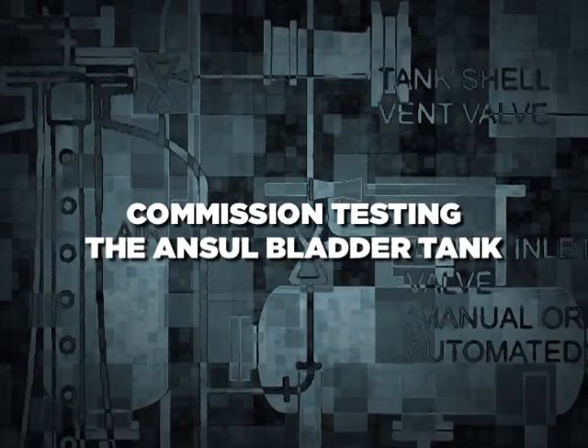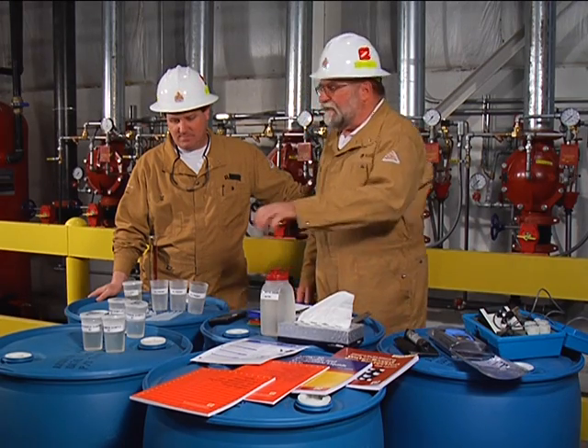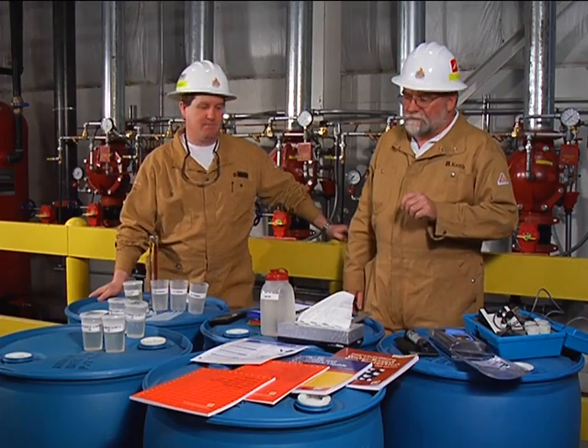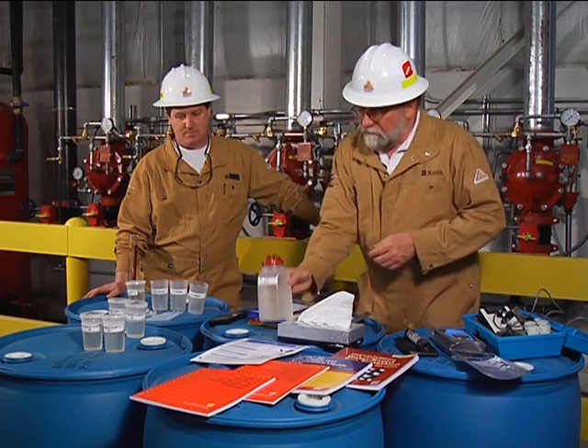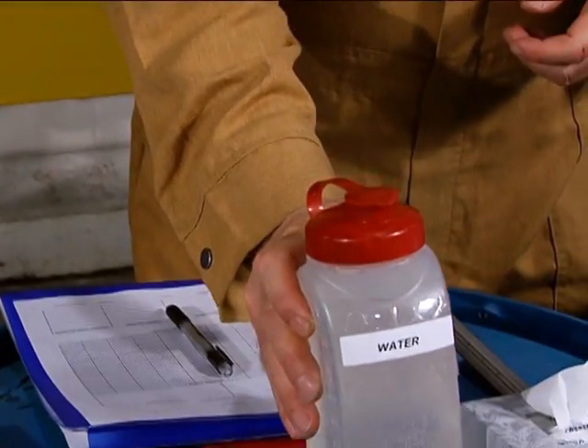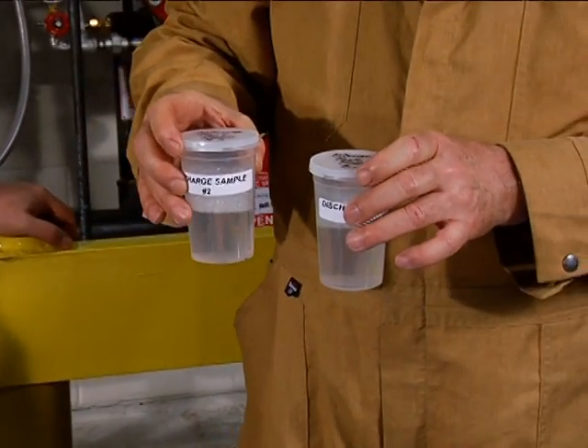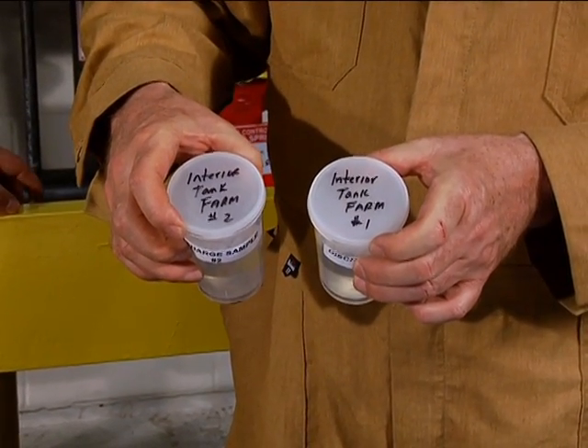Commission testing the Ansul bladder tank. We've completed the discharge test through the hose monsters and play pipes outside of the facility, and we're now ready to test for the concentration percentages of those discharge samples. We've taken samples of the concentrate from the foam bladder tank, a sample of the fire water used to support the design of the system, and from the discharge test done yesterday, the interior tank farm foam discharge samples — sample number one and sample number two.